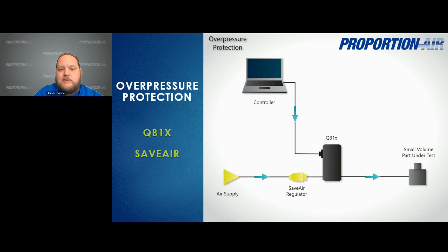Output pressure is easier to control when supply pressure starts closer to the desired output pressure. When there is high pressure differential between supply and output, the inlet valve may not operate fast enough to prevent large set point overshoot and instability. Repeated or sustained large overshoot can lead to sensor damage. A miniature regulator like the SaveAir lowers the pressure of air coming into the EPR to a preset limit, protecting that internal sensor from overpressurization and reducing overshoot or instability.